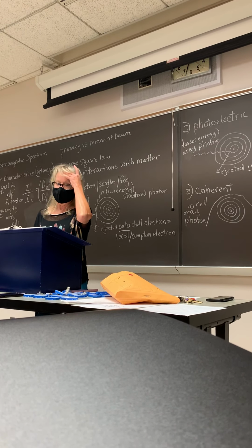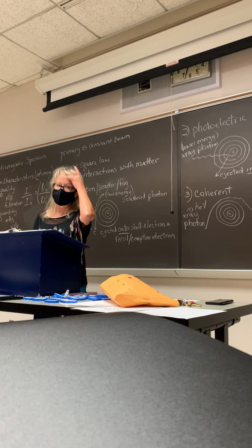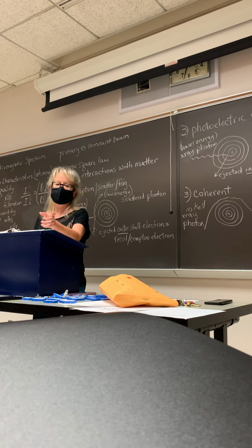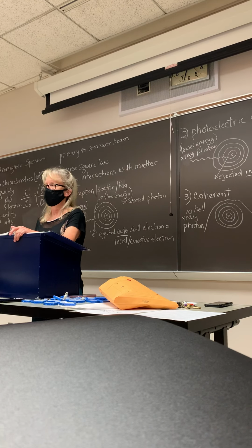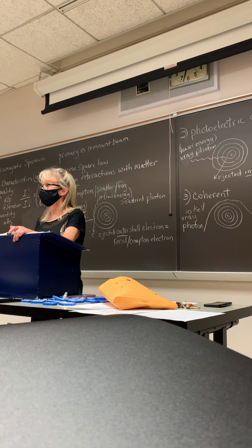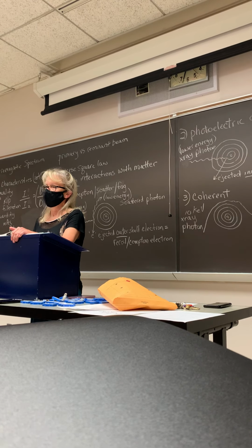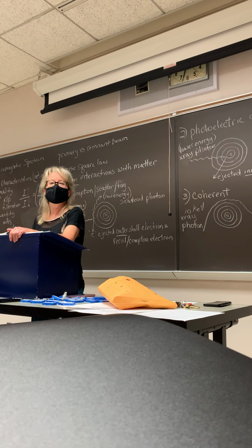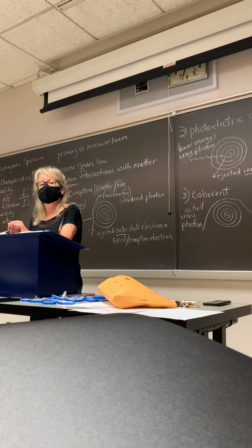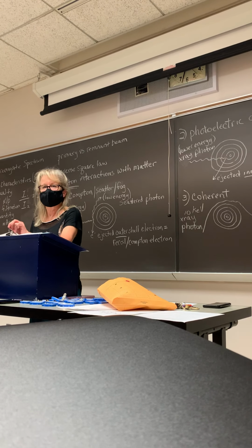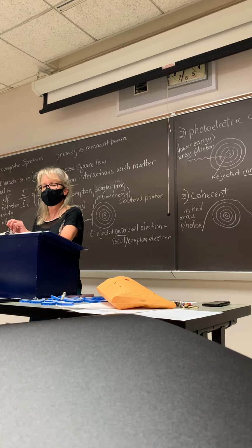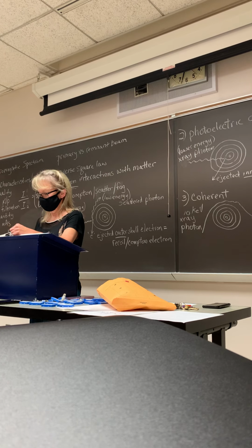To protect yourself, if you're doing fluoro, how should you stand as far as the table is concerned to decrease your dose? Remember? You should stand at a right angle to the patient or the table, or 90 degrees.